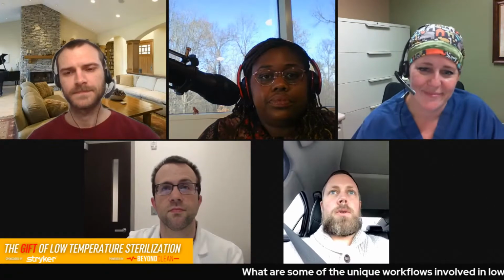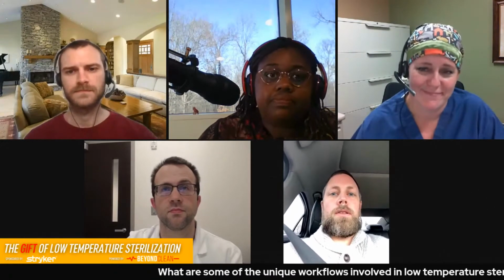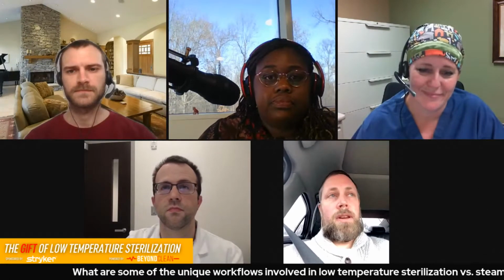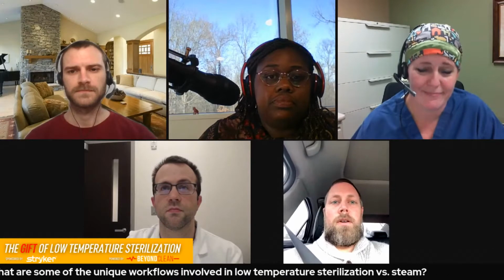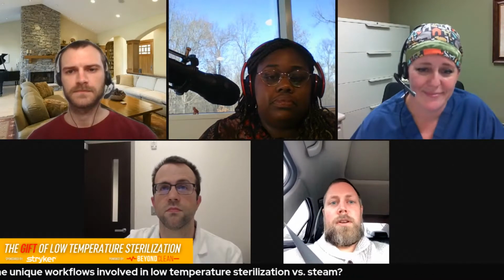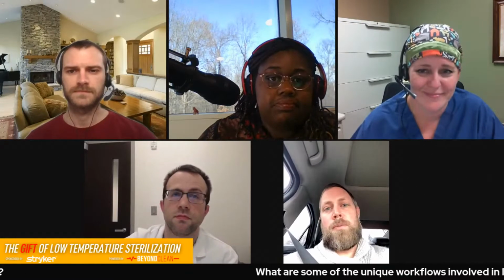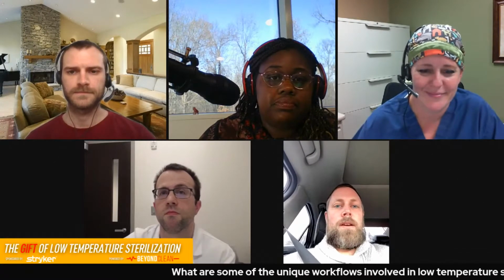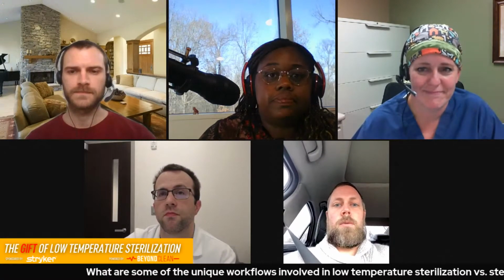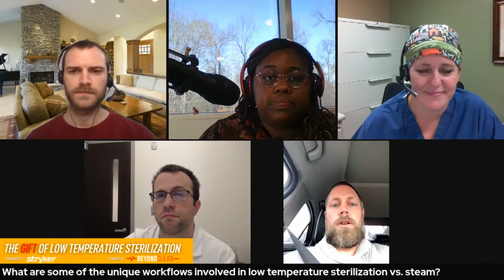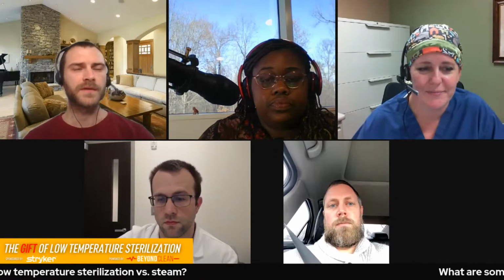So I think the biologicals are a factor that we're all missing out on. I think the biologicals are much more intricate and demanding on, did it meet this criteria, which is exposed for this long, versus steam, which only has to hit for 4 minutes and it should kill off all the spores. But with low temp, I think there's a lot more factors that we should incorporate into that education piece too. Yeah, for sure. And as we get into education in a bit, that'll be fun to dive into.